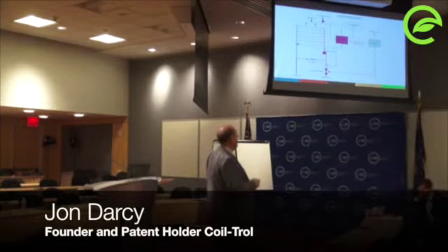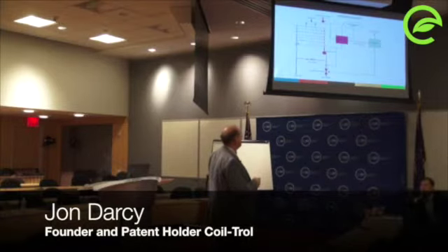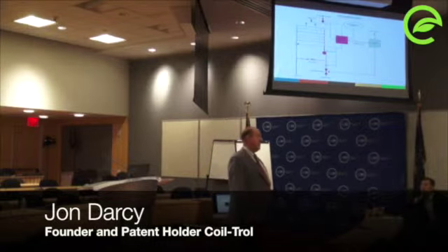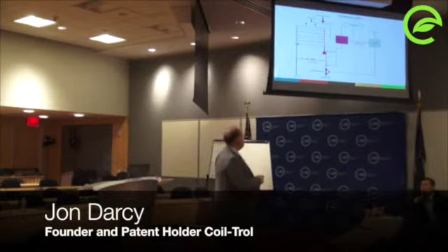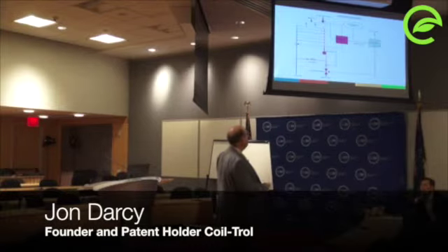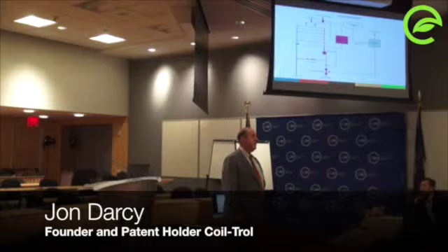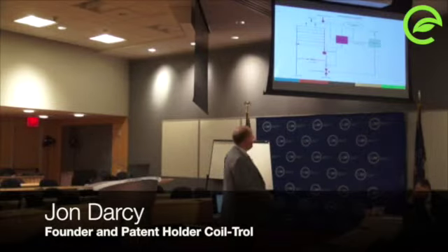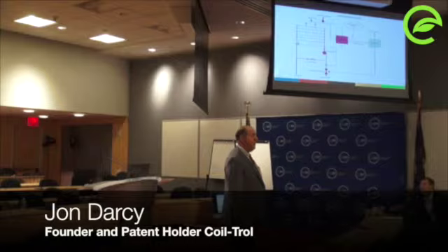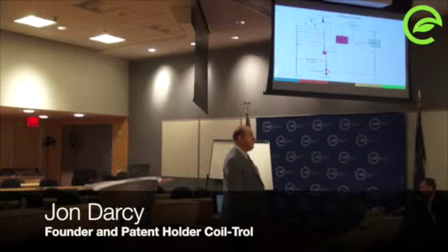And then you have the cost of a few temperature sensors. That temperature and humidity sensor is critical. That's got to be a good sensor. You can buy a good temperature sensor, and by good I mean they'll guarantee accuracy for 5 years, for $250. Not a lot of money. If you need 20 of them in a building, at $250 a piece, you just spend $5,000 and that's it. That does the whole building.